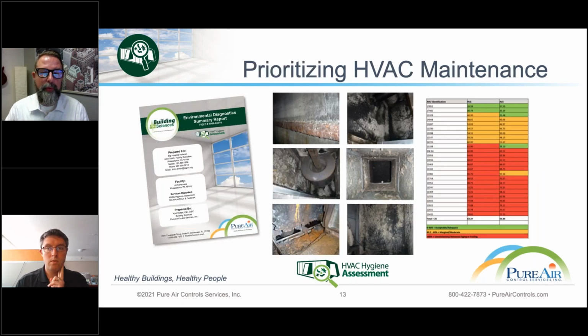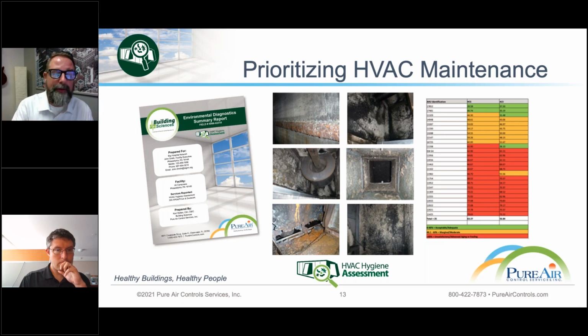That's a really great point. And as you alluded to before with dust, one of the key constituents of dust is human skin cells, which are a food source for different kinds of bacteria. So oftentimes, facility managers and HVAC techs will go in to do maintenance on a fan belt or something, open the door of the unit after shutting it off, and it just smells like body odor or dirty sweat socks, or maybe that odor is getting into the occupiable space. That's probably a good sign there's bacterial growth in there because of this buildup, dust getting into the biofilm, bacteria eating it.